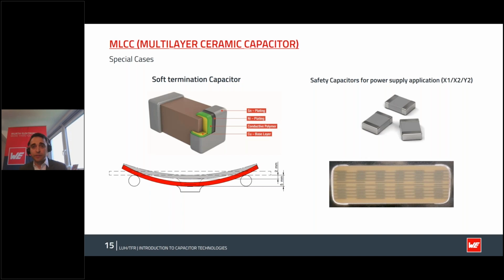Normal parts can be bent on a 10 centimeter PCB down to 2 millimeters, and these soft termination capacitors can be bent 5 millimeters on the PCB. Apart from that, there are also safety capacitors, with X1, X2, and Y2 safety classes. I'll define them in a minute together with the film capacitors. And you can see on the right, the internal structure is basically multiple capacitors in series. This way, we can limit the likelihood of a failure mode ending up in a short circuit.